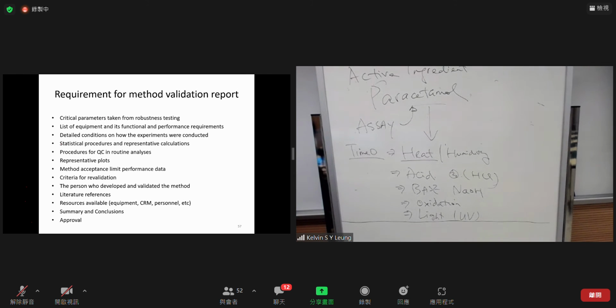Okay, so you have to do some conclusion in the reports. It's not just the report. Here is the linearity, here is the precision data, but you don't have any conclusion. No, you need to, even though you noted it's passed, you have to draw some conclusion.